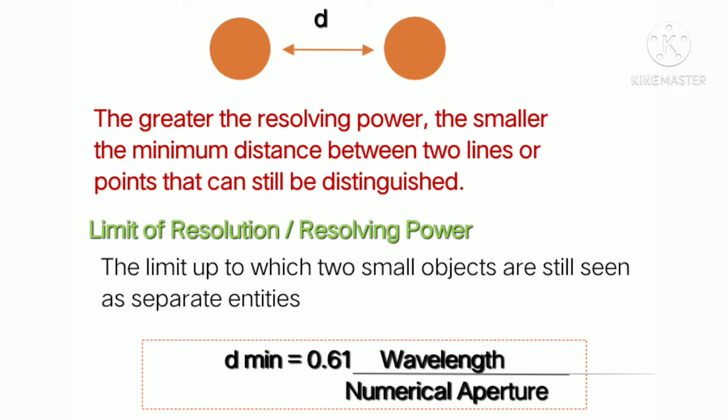Always remember: greater resolution means a smaller distance between two points or entities. The limit of resolution, or resolving power, is the limit up to which you can identify two objects in an image as different entities. The formula for this is: distance = 0.61 × wavelength (λ) / numerical aperture (NA).